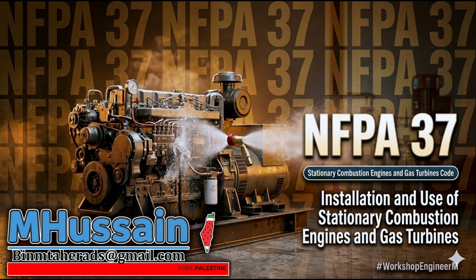So exception 2 says you can completely bypass those minimum distance rules, the 25 feet and the 3 feet, if you meet two conditions. Okay, what's condition 1? The generator has to be in a weatherproof enclosure made of non-combustible materials. Easy enough. Most commercial units come in steel or aluminum boxes anyway. What's the catch? Condition 2. It must be demonstrated that a fire inside that enclosure will not ignite combustible materials outside of it. Demonstrated. That sounds incredibly subjective. It is entirely subjective. The code gives no specific parameters for how to prove this.